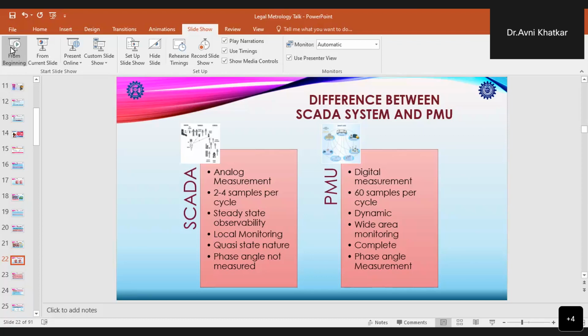we can measure the dynamic nature of the grid, and this streaming data which is collected from multiple PMUs can be used to develop customized sophisticated algorithms which can be further used to allow the load dispatch computers to completely and continuously monitor the grid at the regional levels and automatically perform the task of islanding, load shedding, and disconnecting the zones which can cause any disruptions and potentially threaten the stability of the grid. So by using phasor measurements in the grid, we can ensure optimum grid synchronization and may also use the grid effectively by having islanding detection systems, system blackout restoration, microgrid management, by enabling the power system operation to optimize the energy, and we will also have cost efficiency of the grid in this way.